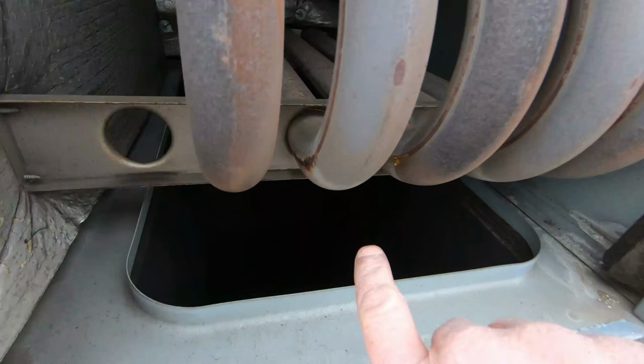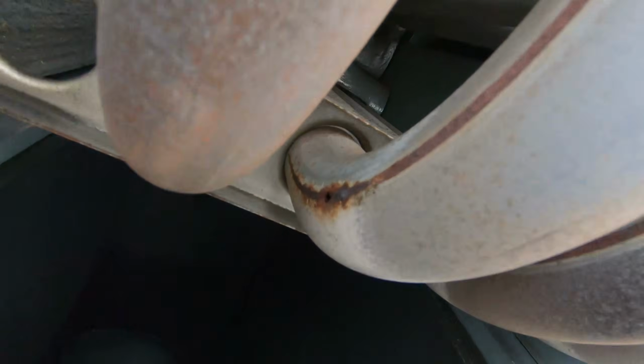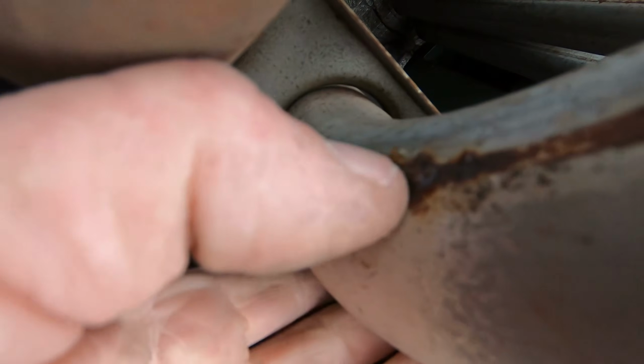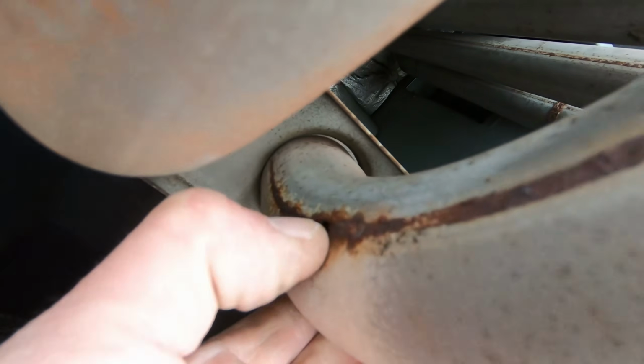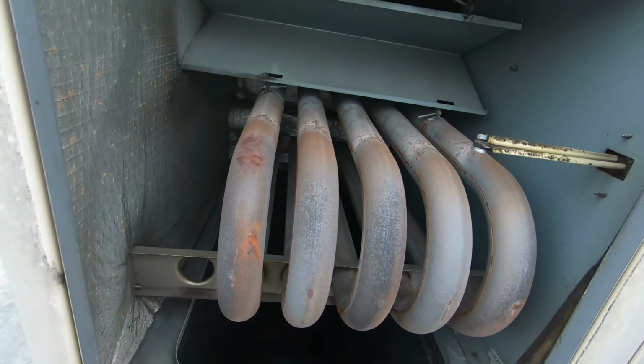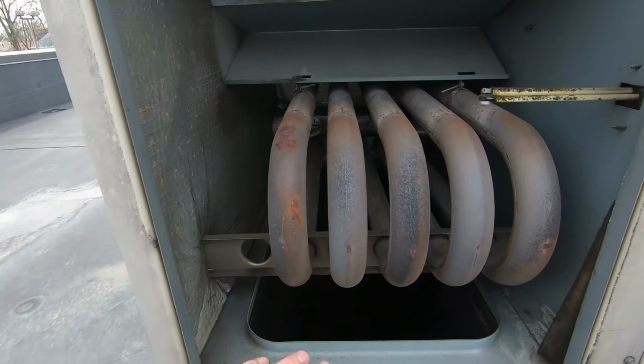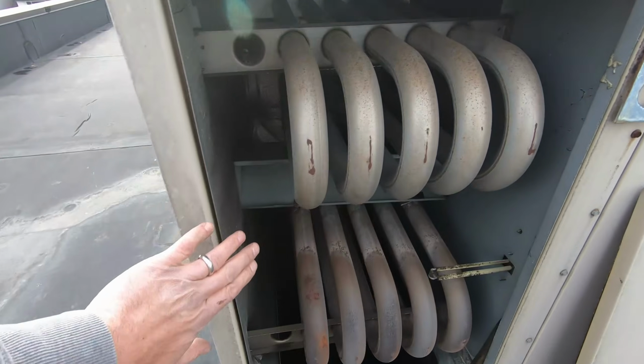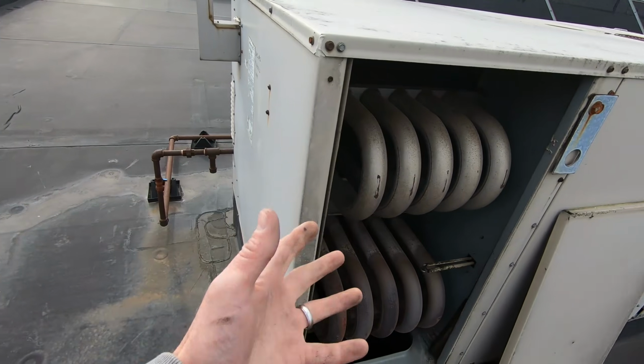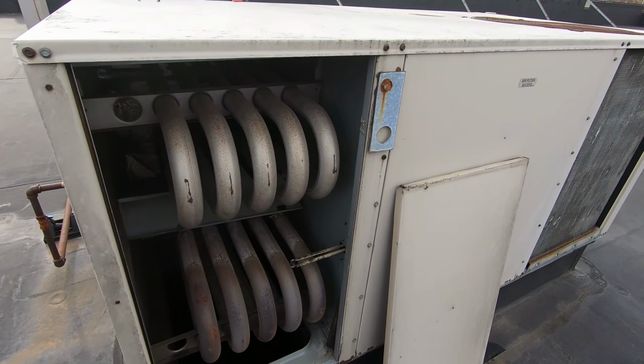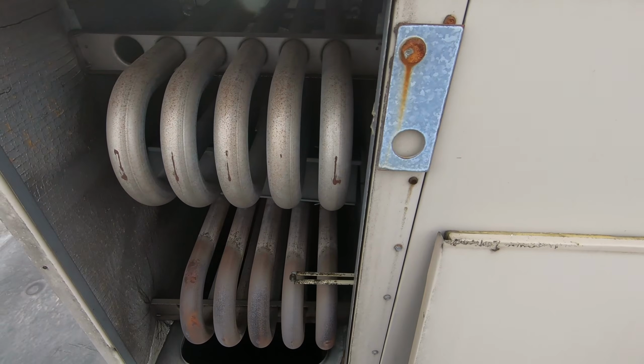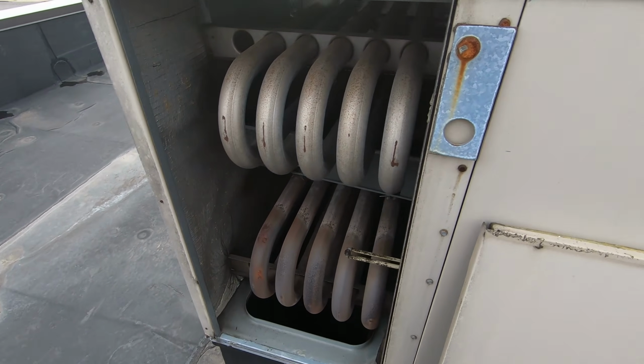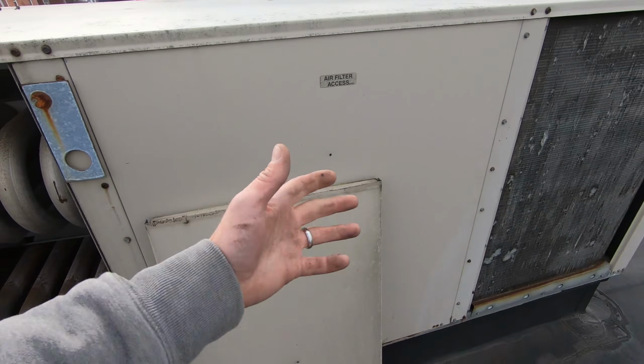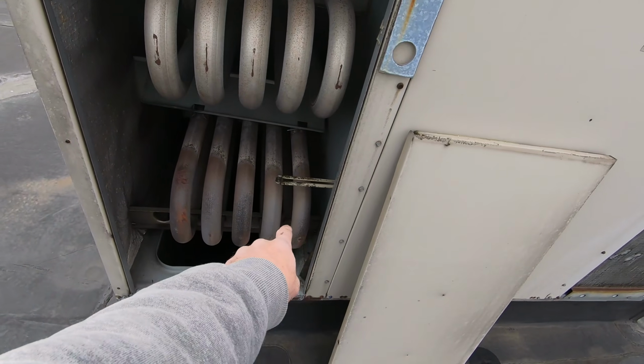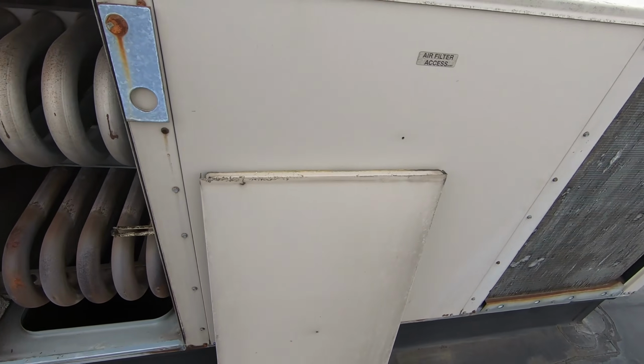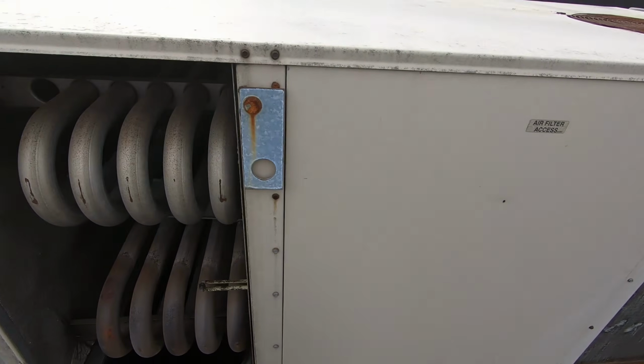And again, right here it is—a pretty good sized little hole there. So these are actually a decent heat exchanger to replace. You take this back panel off, take this whole side off, and the whole thing just pops right out. Other than the carrier units, these are really pretty simple. A lot of times you've got to pull the economizer off to get to some of these screws, but there's no economizer here, so this should be a nice easy day.